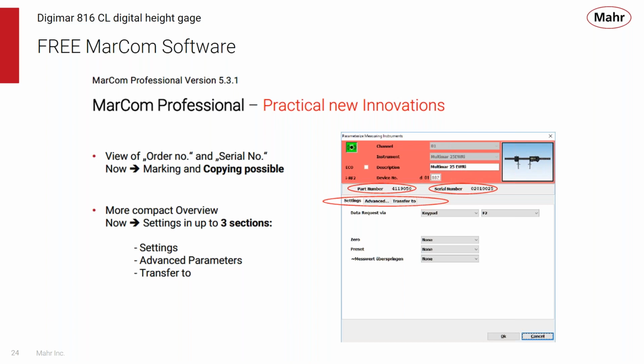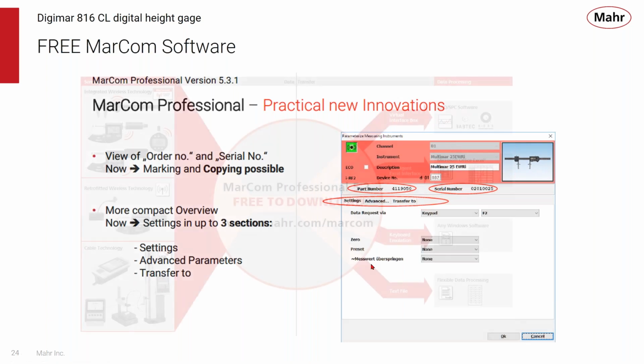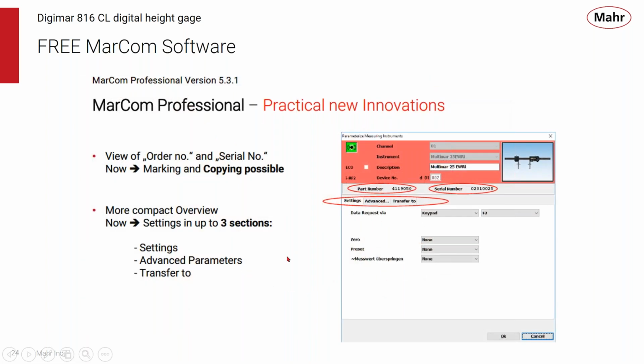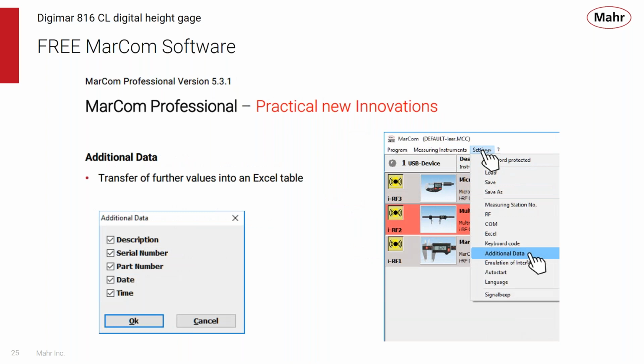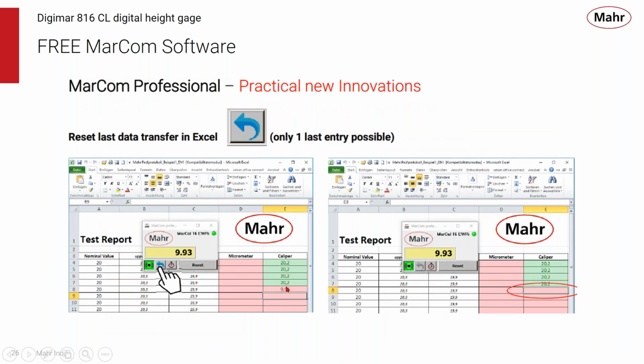We're always updating MarCom - we're up to version 5.3.1 now, doing things that make data collection more valuable to the user. One of the most important features is that we can assign a gauge number and a part number to the device making the measurement. Now we can tie the measurement data to the gauge along with the time and date, collecting all that information as part of the standard measuring routine - the description, serial number of the gauge, part number, date, and time.